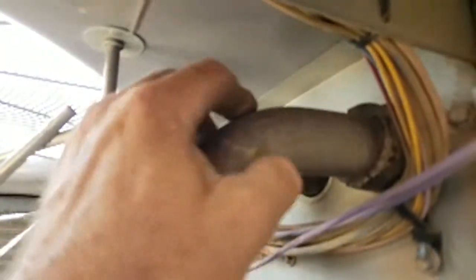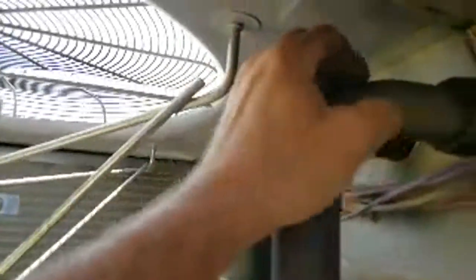With everything that's in one of these units, that short could have been a lot worse. As soon as I went in here and pulled that, I had my little meter beeping with the wire isolated and just walked right over, shaking the wire, and found it fast. Look, you can see where it's been rubbing on the copper. It's actually an indentation in the copper from this cabling. Crazy, huh? Be a lot of refrigerant to drop. So yeah.